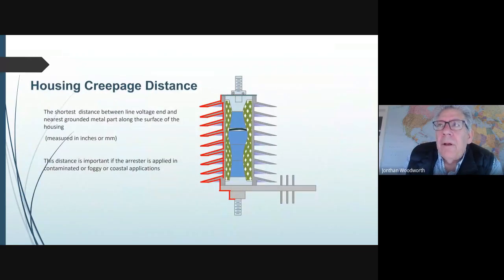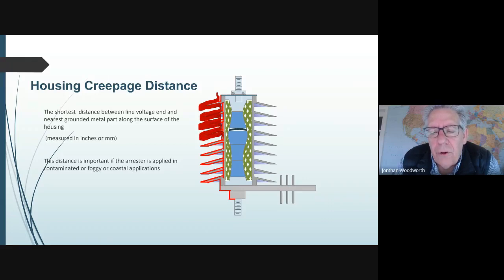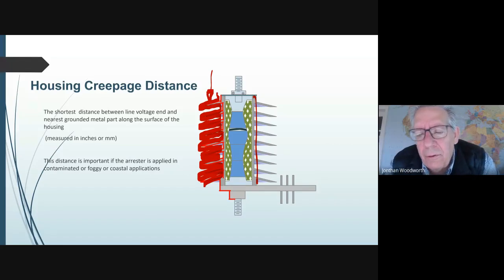We'll skip that one because, well, not really. All insulators, whether it's an arrestor or whether it's just a plain insulator, have this thing called creepage distance. And if you draw a line over the surface, over all the sheds or skirts, this distance is much longer than a straight line. And this creepage distance is used primarily to keep this insulator from flashing over when it's wet.